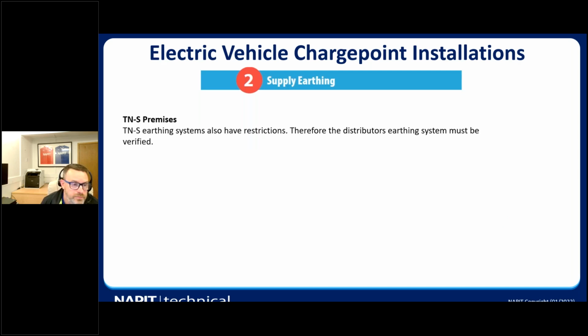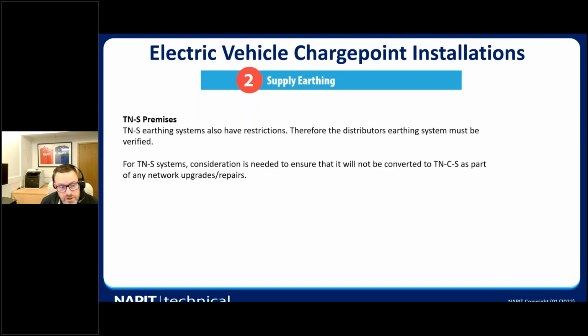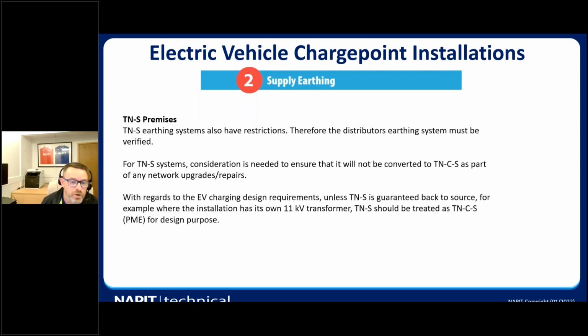TN-S premises, the TN-S system does have some restrictions as well, and the distributor's earthing system must be verified. For TN-S systems, consideration needs to be given where the TN-S system hasn't been converted to TN-C-S as part of any network upgrades and repairs. And it's difficult to make sure you could fully cover that because it's difficult to confirm back to the source that it's still a TN-S system unless the installation has got its own transformer.